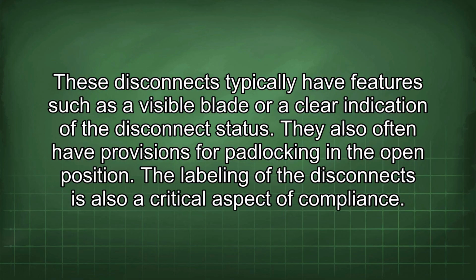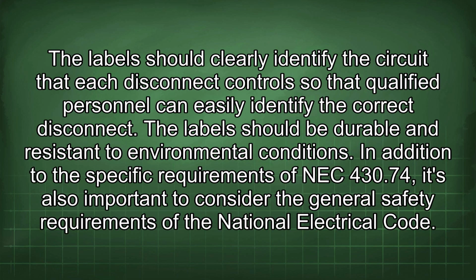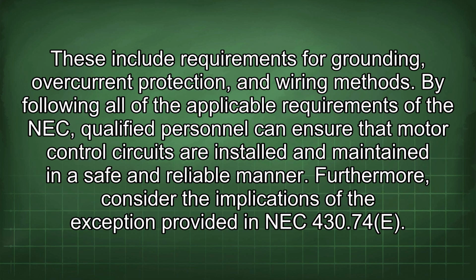The labeling of the disconnects is also a critical aspect of compliance. The label should clearly identify the circuit that each disconnect controls so that qualified personnel can easily identify the correct disconnect. The label should be durable and resistant to environmental conditions. In addition to the specific requirements of NEC 430.74, it's also important to consider the general safety requirements of the National Electrical Code. These include requirements for grounding, overcurrent protection, and wiring methods. By following all of the applicable requirements of the NEC, qualified personnel can ensure that motor control circuits are installed and maintained in a safe and reliable manner.